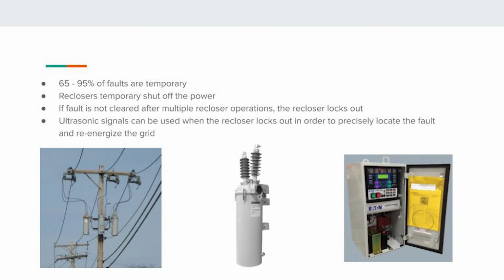According to Eaton Cooper Power, a large manufacturer of power equipment, a majority of faults are temporary. These temporary faults are easily cleared through the use of a recloser. After a fault is detected, a recloser opens and closes multiple times. If the fault is not cleared by the final attempt, the recloser locks out until it is manually reset once the fault is located and cleared. The blackout from the recloser can last several hours, and by the time the fault is located, it may be too late to prevent large fires or damage to equipment.